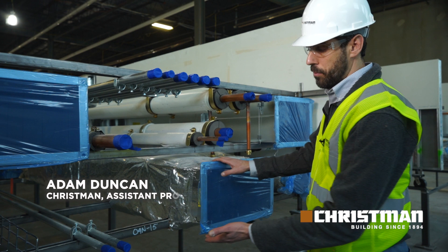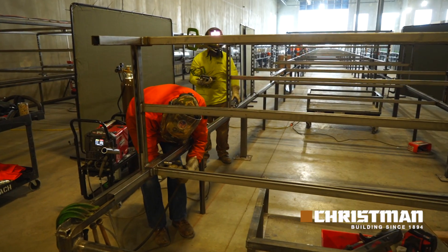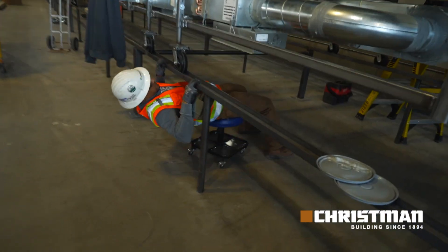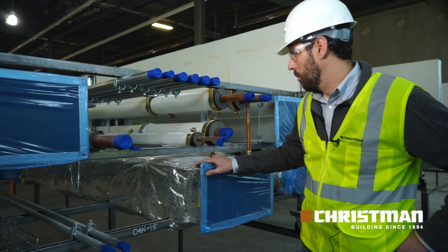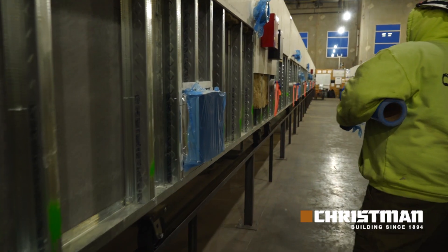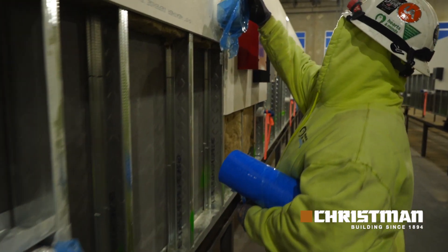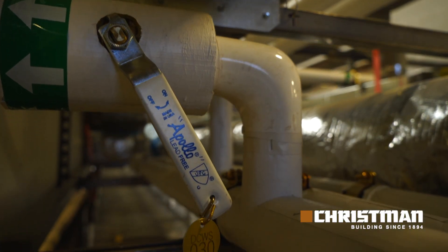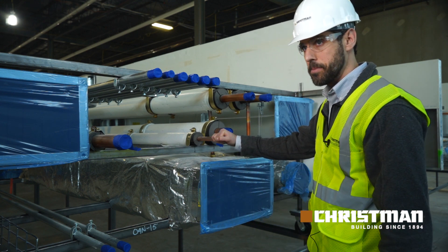Quality-wise you're working between three feet and about five feet, so you don't have to get on a ladder. The guys are able to get around without having to be on a ten-foot ladder, so they have the ability to inspect their work without going up and down. Once all the piping, ductwork, conduit, and cable track is installed, we inspect all the ductwork, cap the ends of the pipe, shut all the ball valves, then set up a test rig and test it to the proper pressure per the specs.